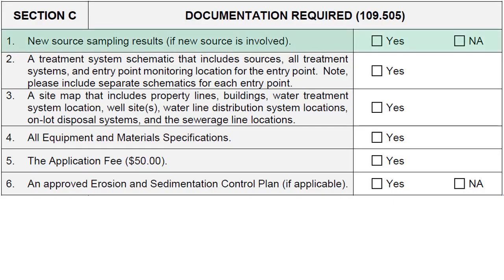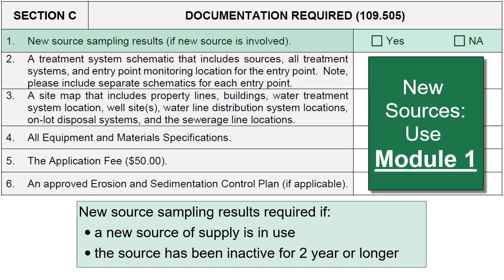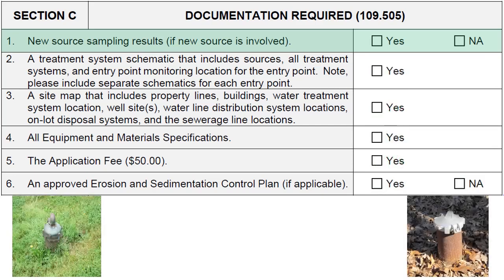The next section on the application, Section C, covers documentation required. This section contains checkboxes to ensure the applicant included all required documentation with the application. New source sampling is required whenever the system is utilizing a new source, or for existing sources that have been inactive for two years or longer. A new source is a water supply that does not have a valid existing PA DEP permit or non-community approval. All new source samples shall be collected under pumping conditions toward the conclusion of the pumping test, when the water quality characteristics are most representative of operating conditions. Please see the links below for proper guidance on new source sampling from non-transient and transient sources.